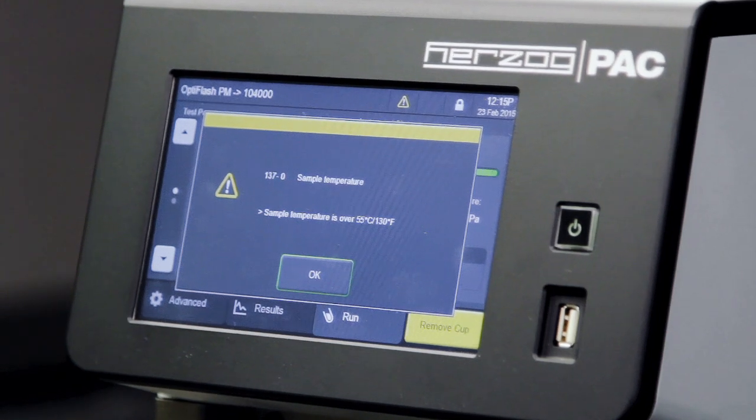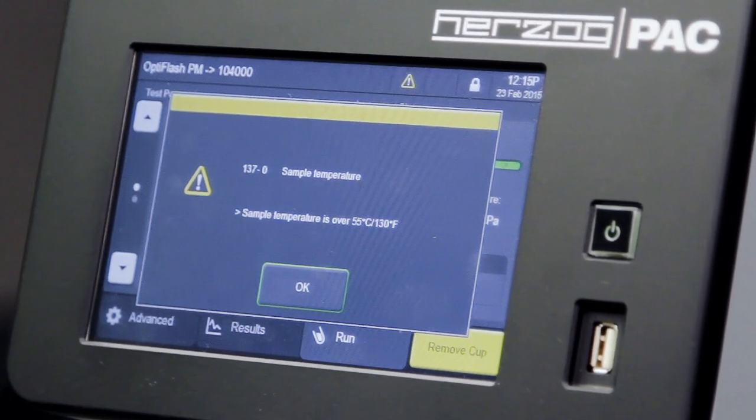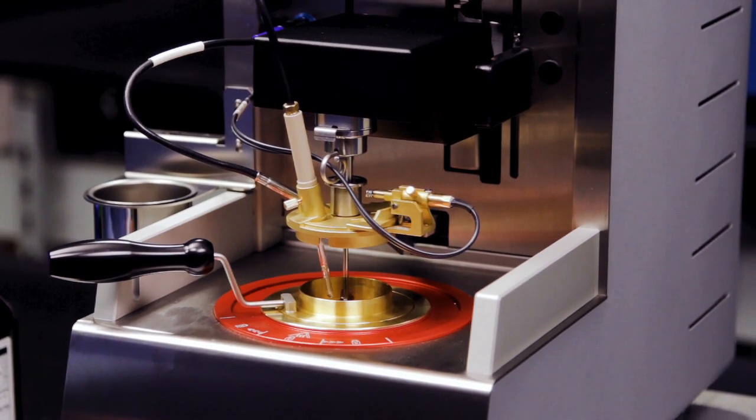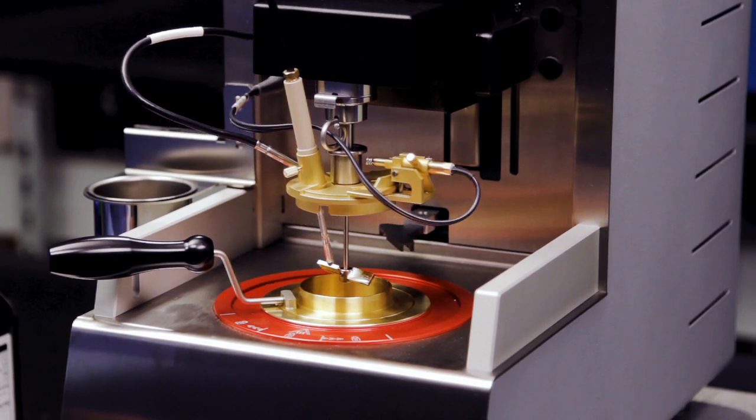A special procedure for high viscous samples keeps them at a standby temperature at the end of the test, which makes it easy to clean even the most difficult sample types, such as bitumen. The innovative design ensures that the sample does not drip from the stirrer into the heater block due to the tilt angle of the arm.